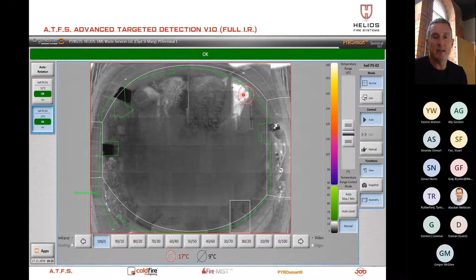Freshly produced material. Ambient temperature in the background is 9 degrees. We can pick up in the background all the glowing hotspots of motors and conveyor belts and stuff. Again, we're not going to go off on those because we've isolated them, but the temperature isn't high enough for us to go off anyway. So if we were to hit 90 degrees on that pile, then the camera system will go into pre-alarm, and then if it should hit 150 degrees, it then goes into the full extinguish and the cannon system goes off.